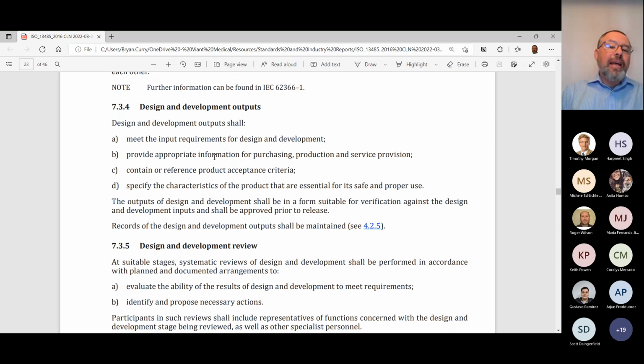We also have to be able to define acceptance criteria for our design outputs so that we know whatever the input was, we have successfully met that requirement. And it also feeds into our verification and validation activities, right? Whatever acceptance criteria we define here in design and development outputs is the acceptance criteria that we're going to have to meet in our verification and validation activities. And then we have to talk about the characteristics of the product that are essential for safe and proper use that are part of the development outputs, making sure that things like usability and efficacy of the device, we have the appropriate outputs that capture all of those things.